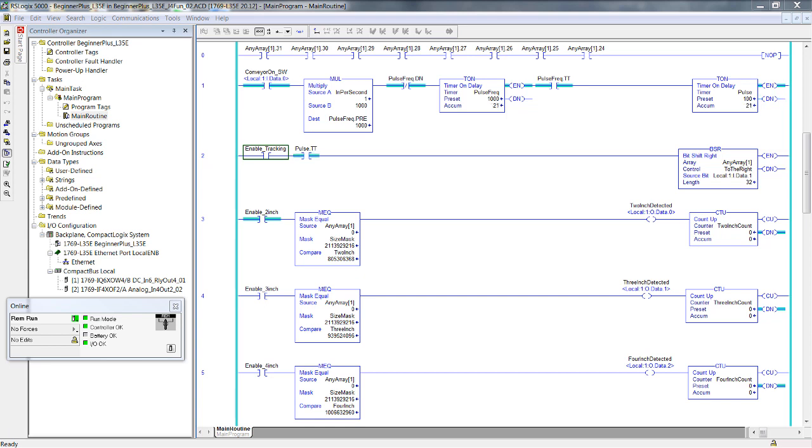Also, we have a device that we use to determine length. Actually, it's a pulse generator that has wheels of a known circumference that ride on the conveyor belt. When you order these pulse generators, you order them by specific circumference of the wheels, and then the pulse generating electronics are ordered by specific pulses per revolution. In order to simplify our application, we're skipping any of the calculations, and we're just stating that this device connected to one of our inputs generates one rising edge pulse per 1 inch of travel of the surface of the conveyor belt. If it puts out 6 pulses, then the conveyor belt traveled 6 inches.